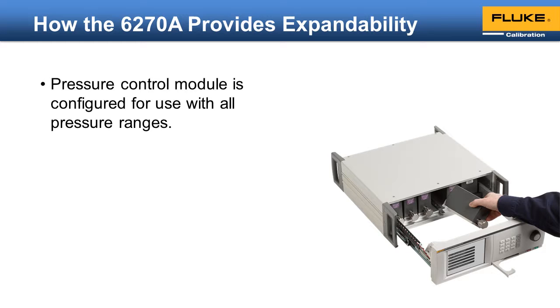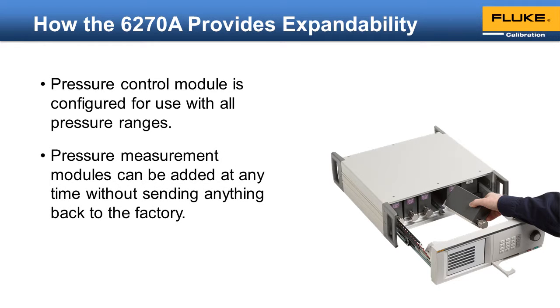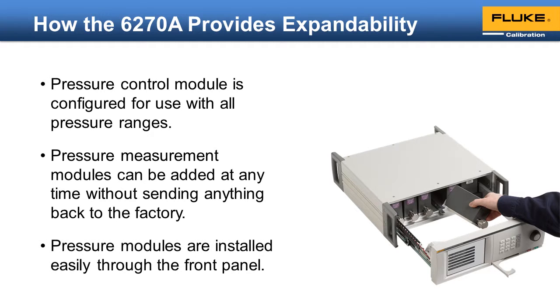Consider a scenario where you purchase a 6270A with just a 100 psi range pressure module. A year later, your requirements expand and you need to cover 3000 psi. When manufactured, the control module was configured to handle 3000 psi even though it wasn't originally required to. So now you can add a 3000 psi module without sending the instrument back to the factory. The pressure modules are easily installed through the front panel, and the 5 available slots make it easy to expand.